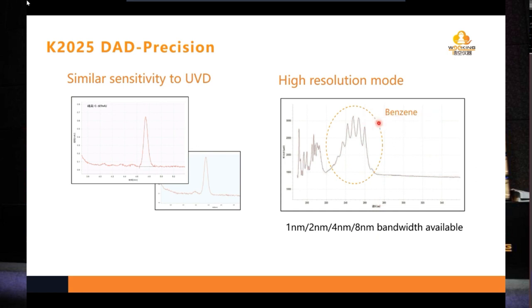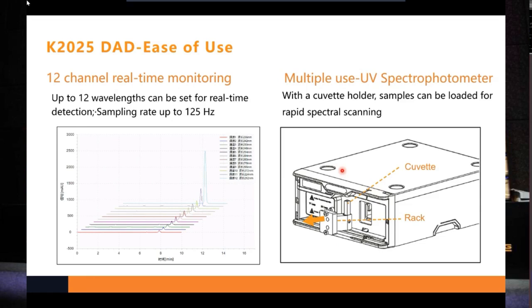This is a spectral scanning of benzene. More peaks can be scanned. There are 1, 2, 3, 4, 5, 6. More peaks can be scanned or can be recognized, means the wavelength is more accurate. And up to 12 wavelengths can be set for real-time detection. The sampling rate can reach 125. With a sample holder, DAD can be also used as a UV spectrophotometer.